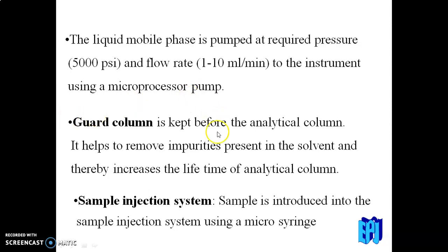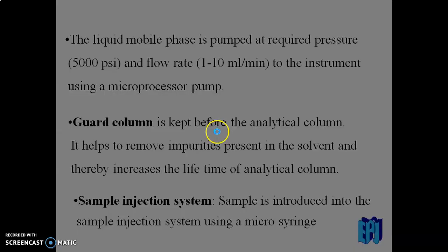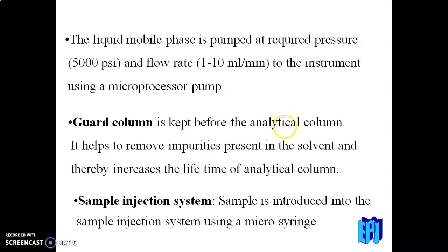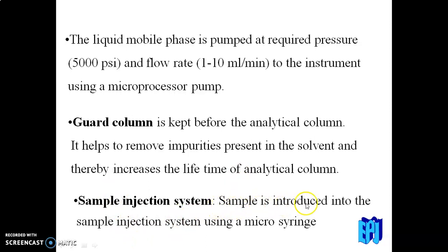The solvent passes through the guard column. The guard column is kept before the analytical column and helps to remove impurities present in the solvent, thereby increasing the lifetime of the analytical column. The sample is then introduced into the system using a micro syringe via the sample injection system (SIS).